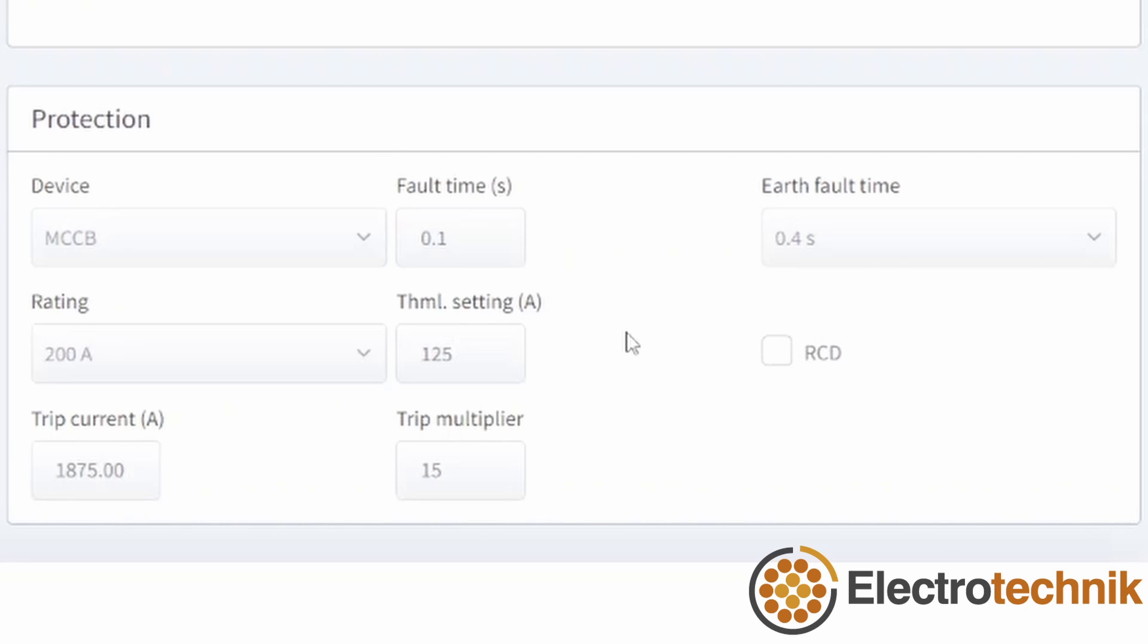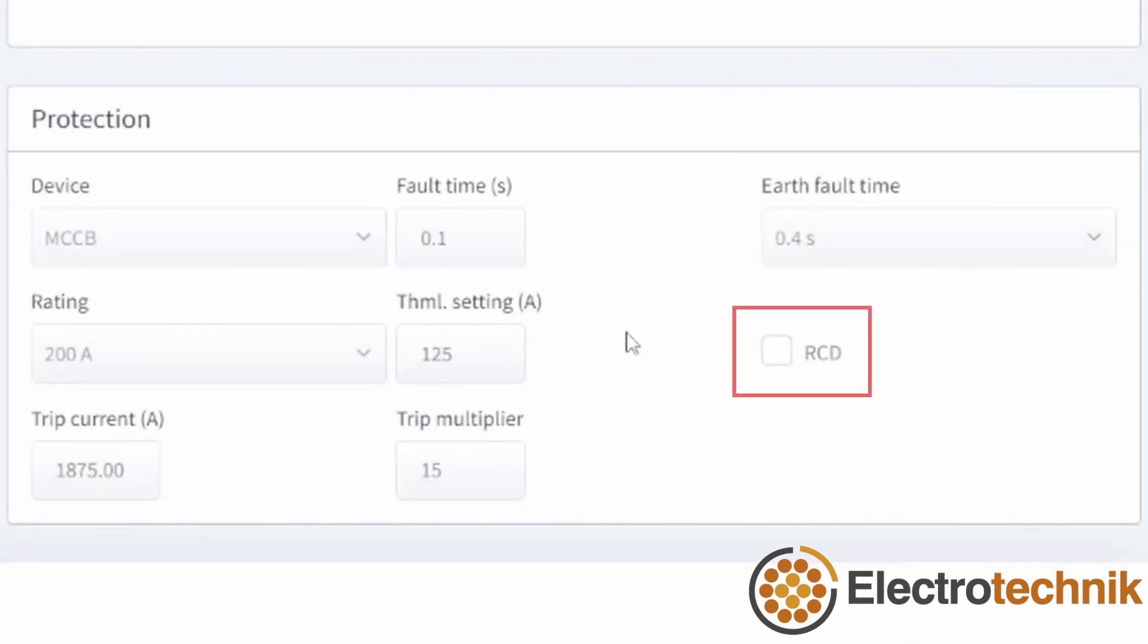The fault time is the time required for the protective device to trip during a short circuit condition and is used for calculating the short circuit rating of the cables. The trip multiplier is a characteristic of the protective device and is set by default but should be taken from the manufacturer datasheet. The trip current is the current required to cause the device to trip within the specified earth fault time and is equal to the rating multiplied by the trip multiplier. A residual current device can also be added that will further affect the fault loop impedance of the circuit.